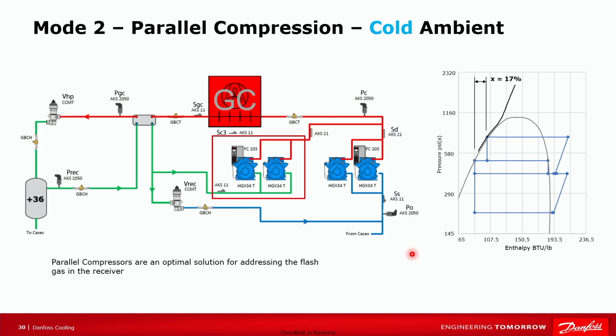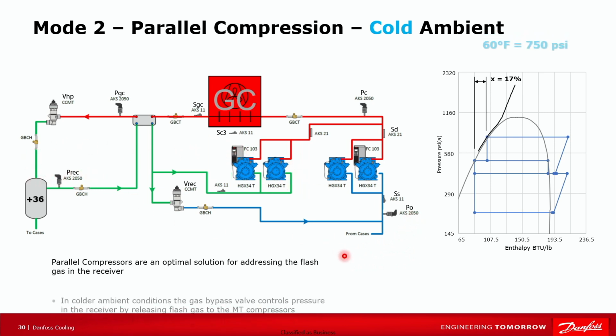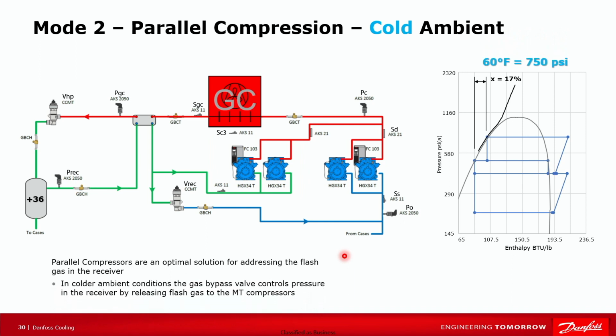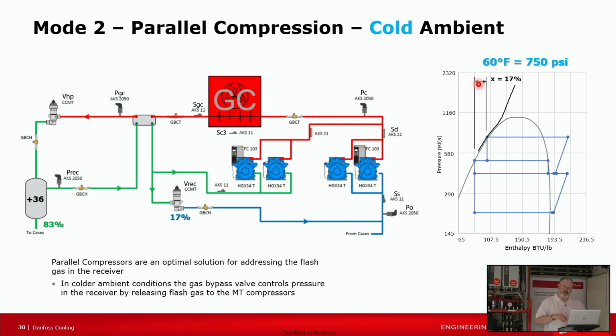What its purpose is, we want to deal with flash gas coming off the receiver in a more efficient way. So on a 60-degree day, we're at 750 pounds. And if you'll notice here, I think we have the percentages. There's only 17% of the refrigerant that had to flash off to get it down to our flash tank pressure.